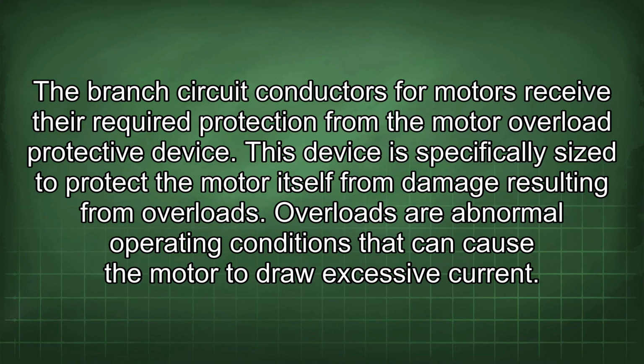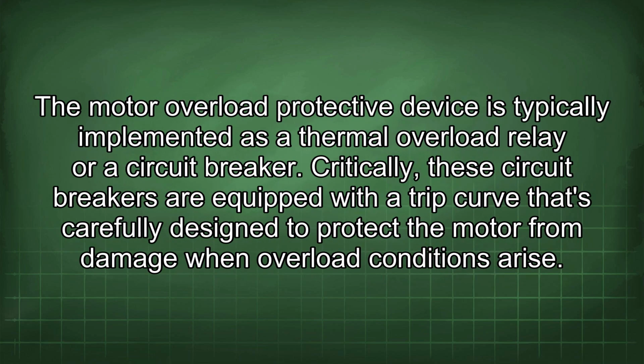Branch circuit conductors for motors receive their required protection from a motor overload protective device. This device is specifically sized to protect the motor itself from damage resulting from overloads. Overloads are abnormal operating conditions that can cause the motor to draw excessive current. The motor overload protective device is typically implemented as a thermal overload relay or a circuit breaker.